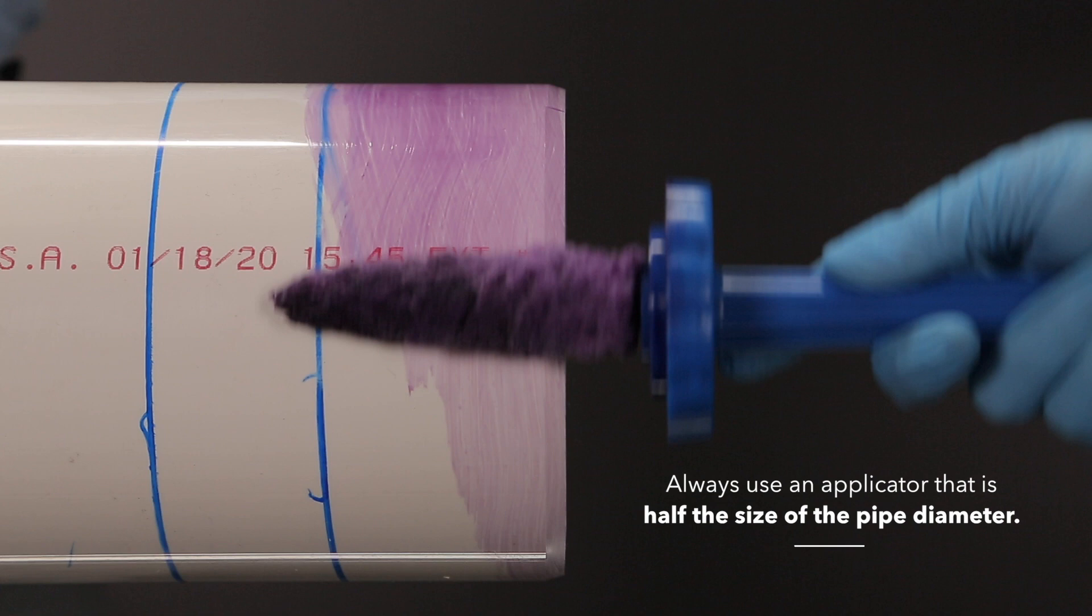No matter what kind of pipe you are joining, you always want to use an applicator that is half the size of the pipe you are joining. So for a 10 inch pipe, you'd use a 5 inch applicator.